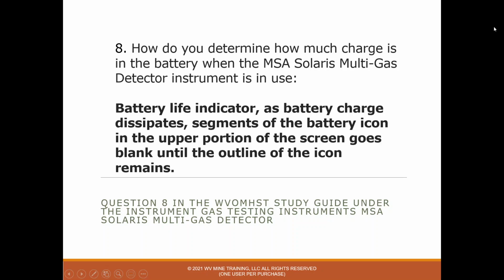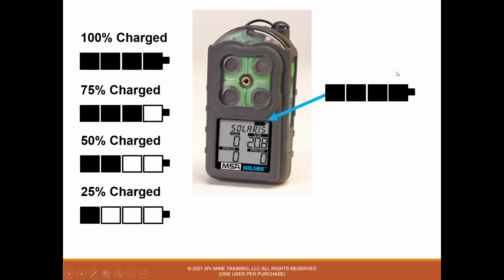Question 8, how do you determine how much charge is in the battery when the MSA Solaris multi-gas detector instrument is in use? And the answer is that it's the battery life indicator. As the battery charge dissipates, segments of the battery icon in the upper portion of the screen go blank until the outline of the icon remains. So here's a picture. Here is a Solaris. You can see the battery, if you can see my pointer here. You know, it's totally blacked in. I have this arrow drawn out here, and I've just got a bigger version of that. But it does have like 4 boxes, and each one of them represents 25% of the charge. So here on the left, if it's 100% charge, all those boxes will be blackened in.